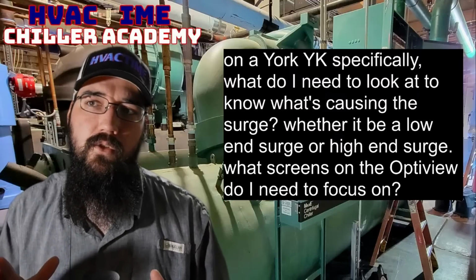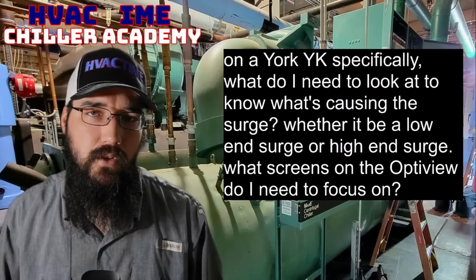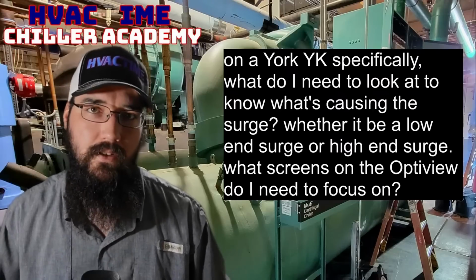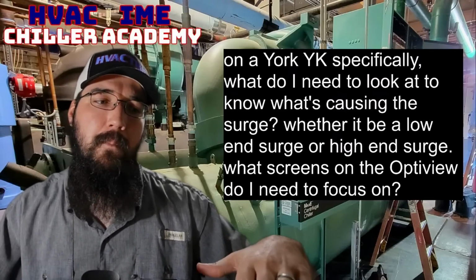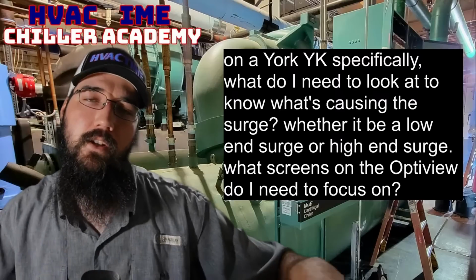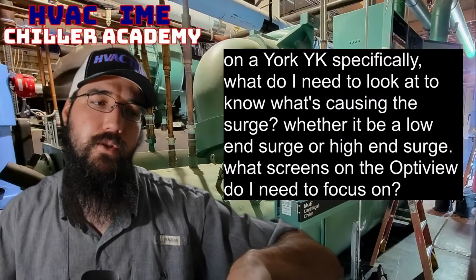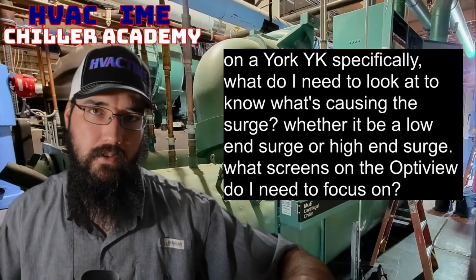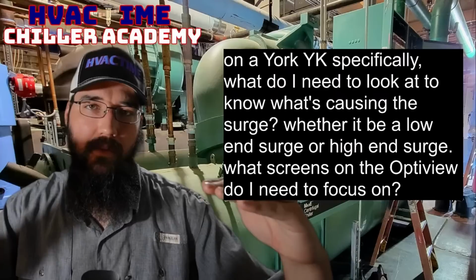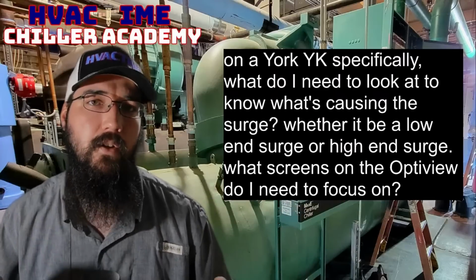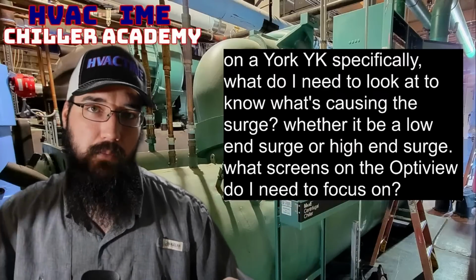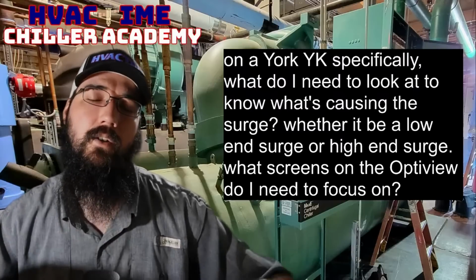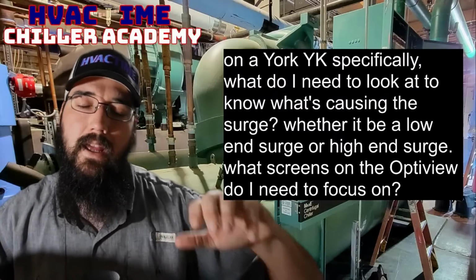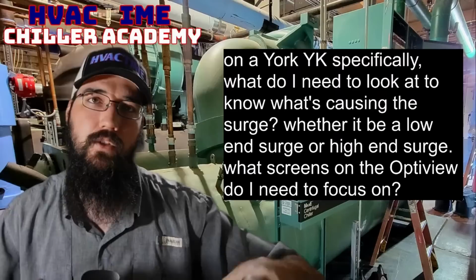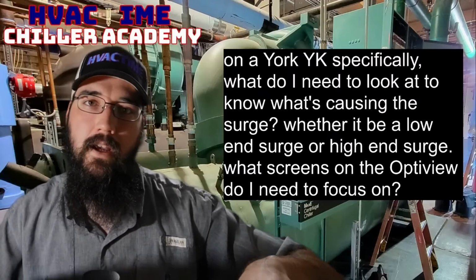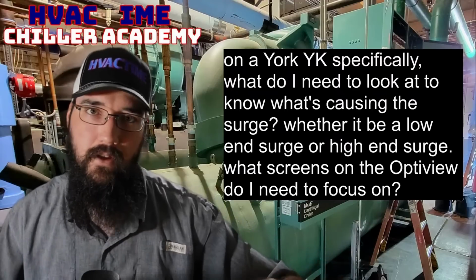Where I see YKs struggle the most is in that low load state. So in that lower load, we really tend to push the surge line quite heavily. And it's largely because the compressor is trying to ramp itself down as much as it can in terms of speed. So it wants to slow the speed down, and the YK is tuned to efficiency to such a degree that it will ride that line really close.